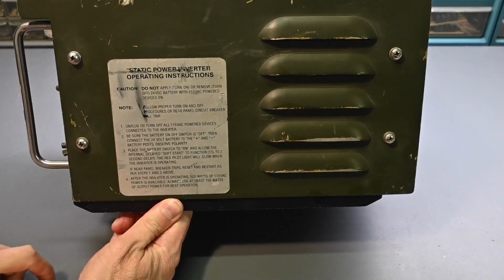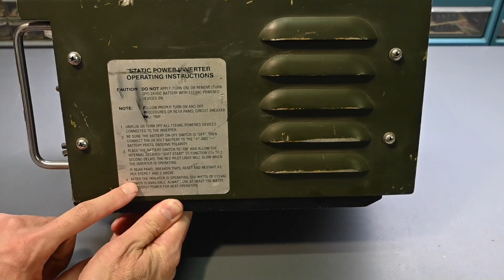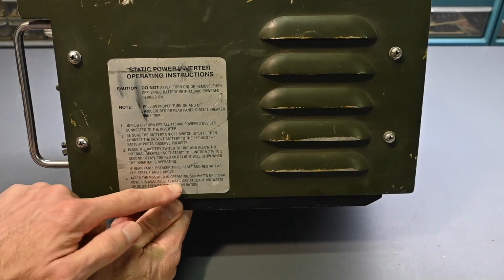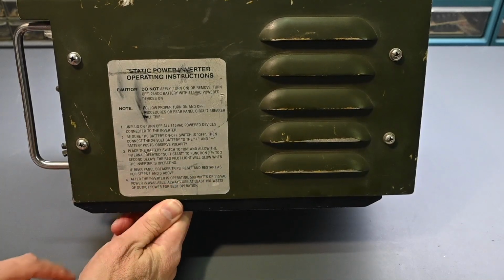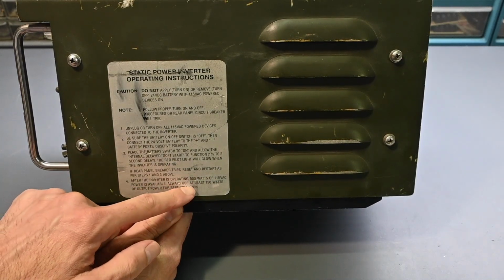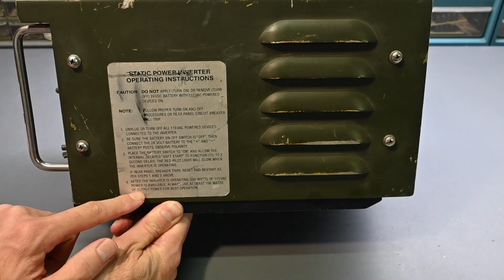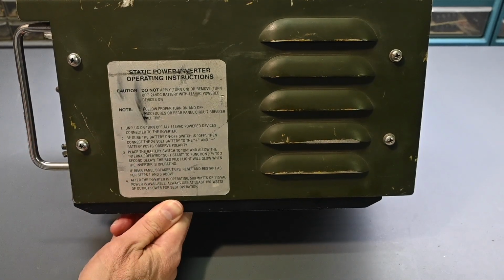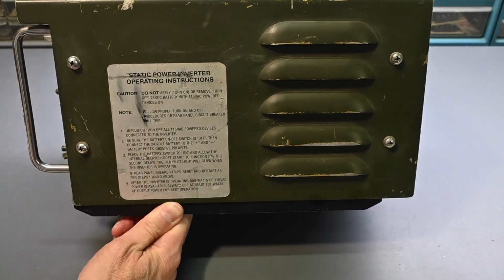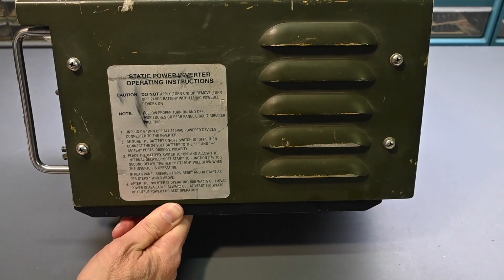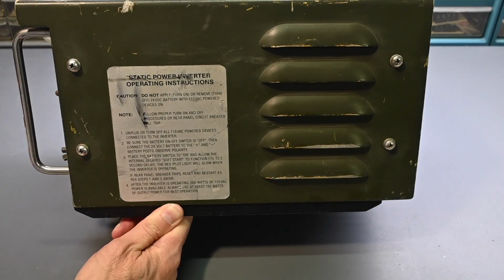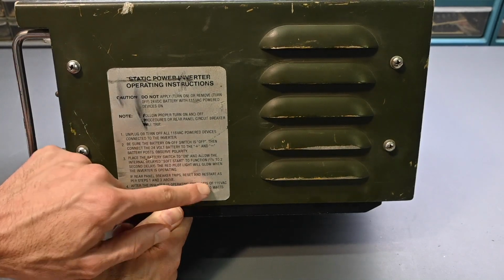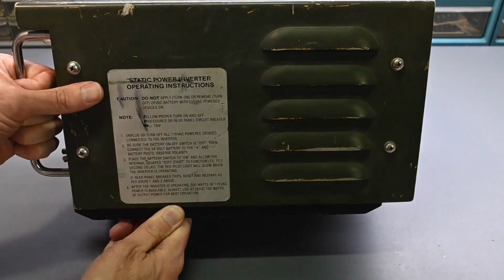All right, so if we take a look right here, you can see some notes about operation, and one thing that's interesting down here, it just says that after the inverter is operating, 500 watts of 115 volts AC power is available. Always use at least 150 watts of output power for best operation. So for some reason they want kind of a minimum load on the inverter. So I'm sure if you don't have a load, maybe the output is somewhat distorted, or it's just not running at its best efficiency, something like that going on. So that's kind of interesting that they do have that note on there.